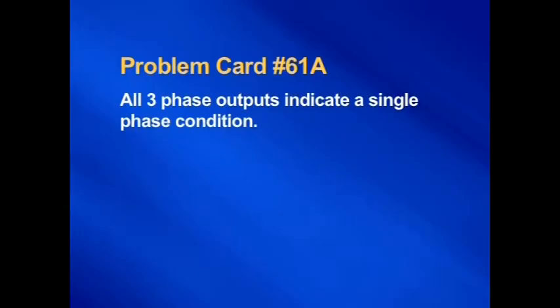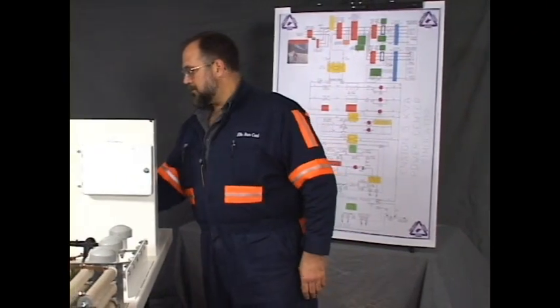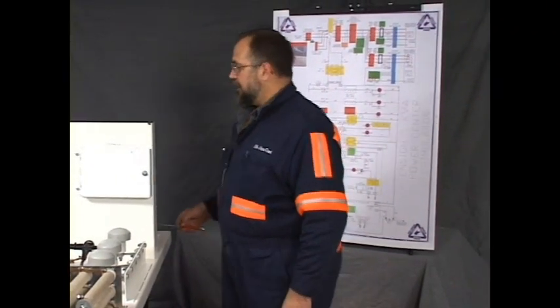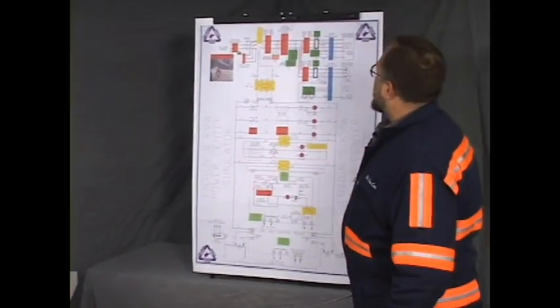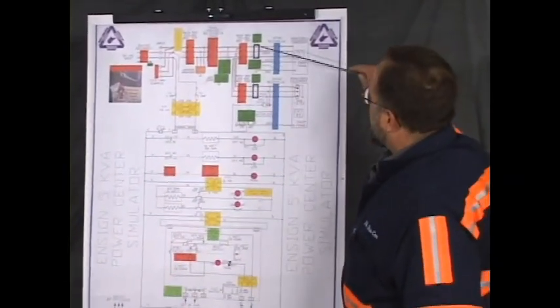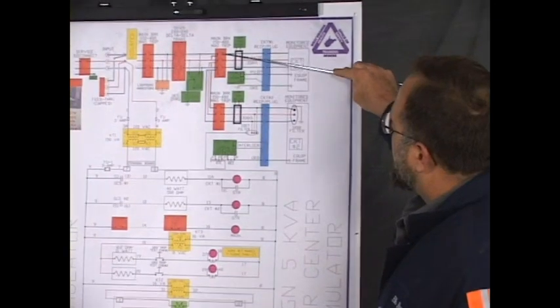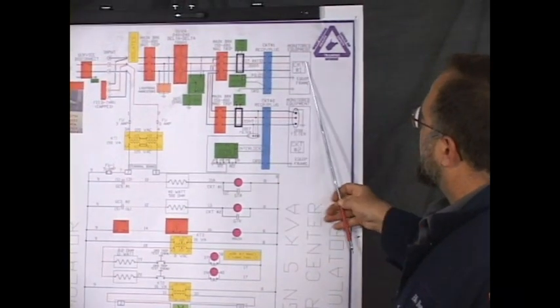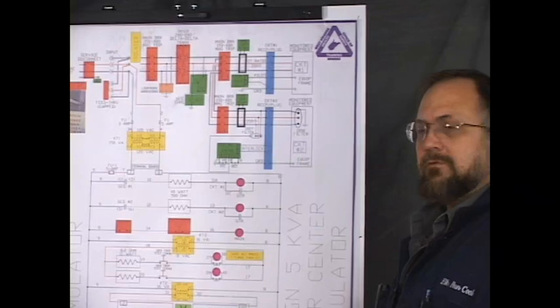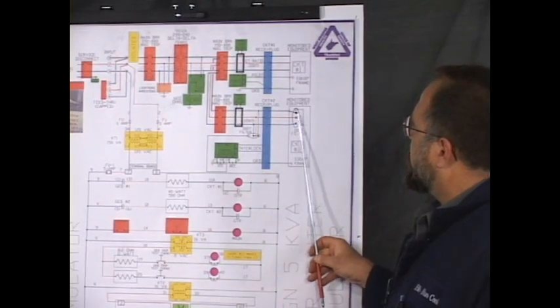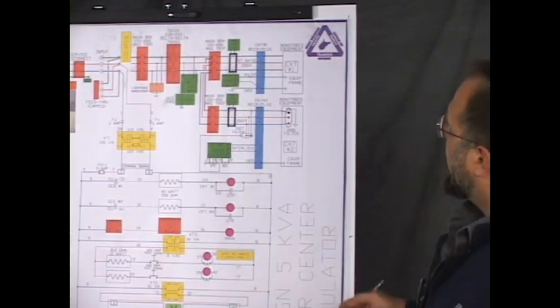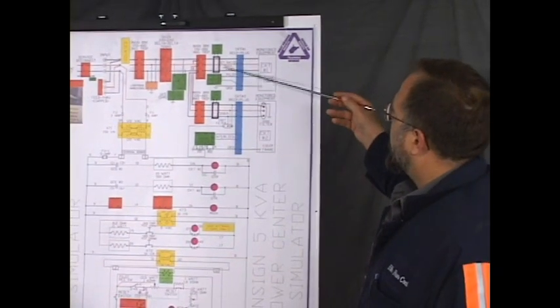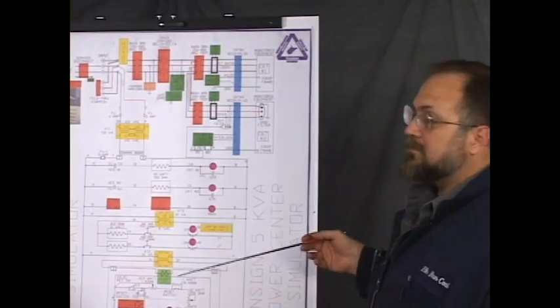The problem is as follows. All three-phase outputs indicate a single-phase condition. Single phase. By saying single phase, that indicates a loss of a phase. The three-phase outputs mentioned are circuit 1, the power circuit going to machine 1, and circuit 2, the power circuit going to machine 2. Okay, it says all the three-phase outputs are single-phased, indicating a loss of a phase.